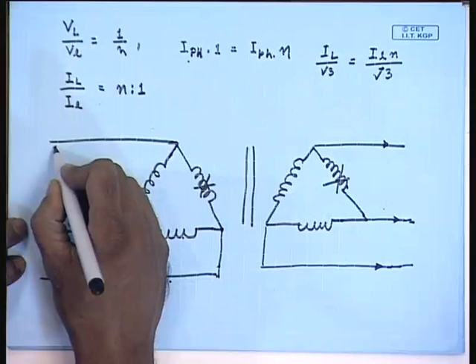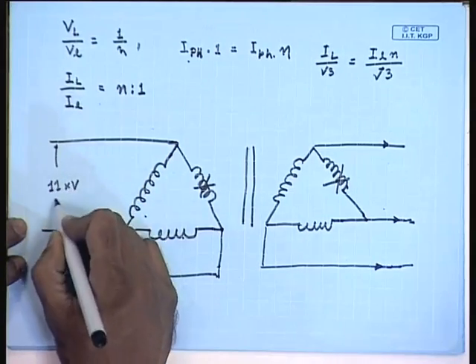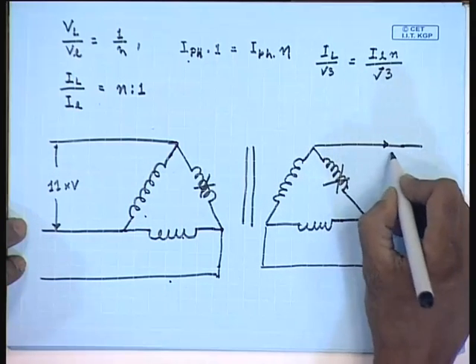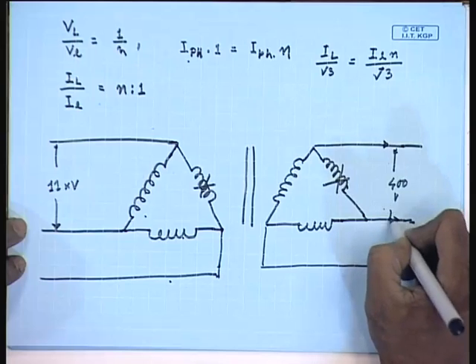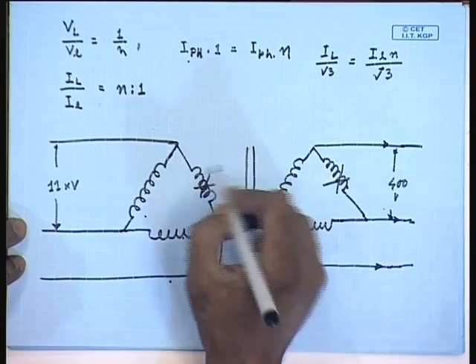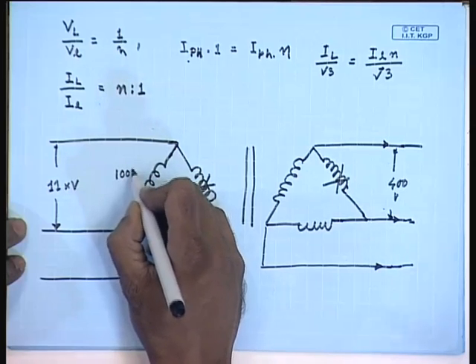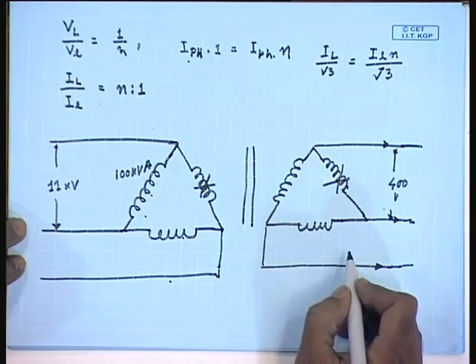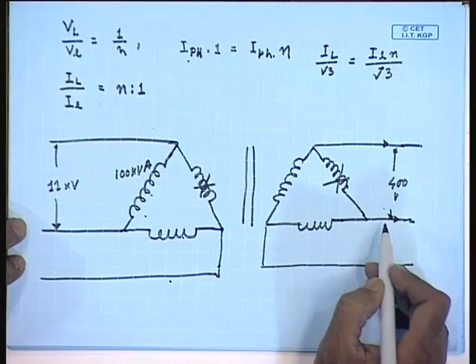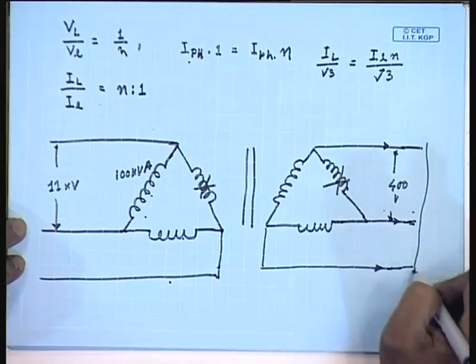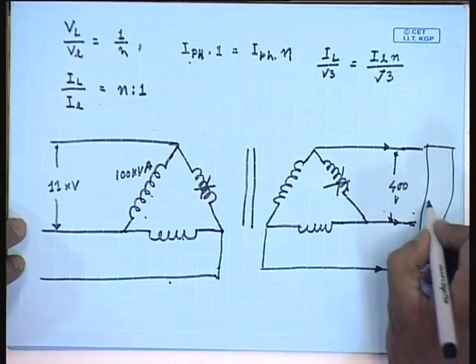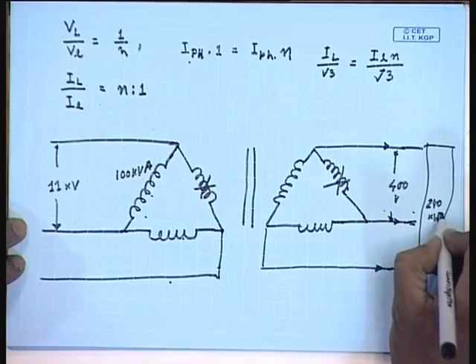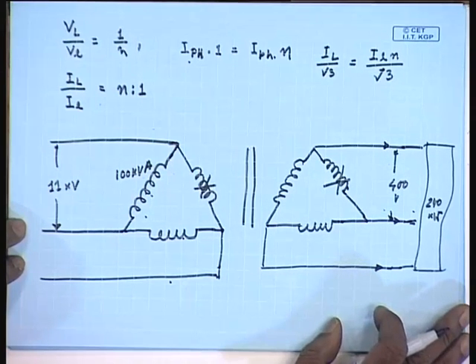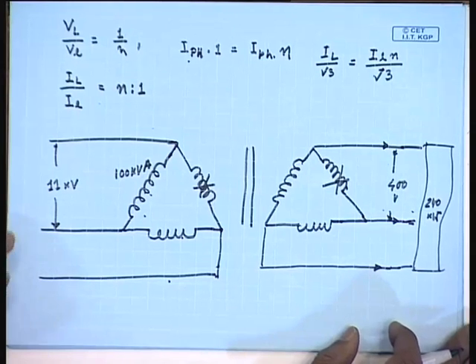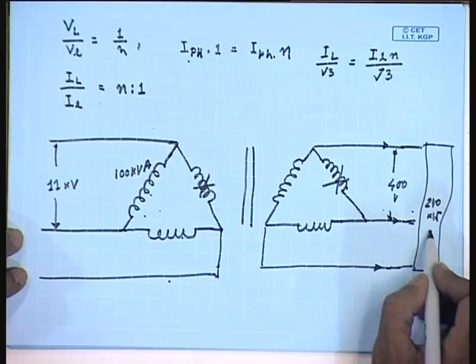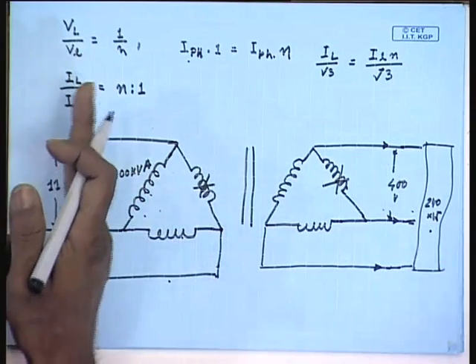Let us say the line voltage for this transformer was 11 kV, and on this side it was 400 volts, and let us say each of these transformers is rated at 100 kVA. This is made of 3 single phase transformers rated at 100 kVA, and it was supplying a balanced star connected resistive load of 240 kilowatt. Assume the transformers to be ideal. Therefore, if this load was drawing 240 kilowatt, then the input load was also 240 kilowatt.